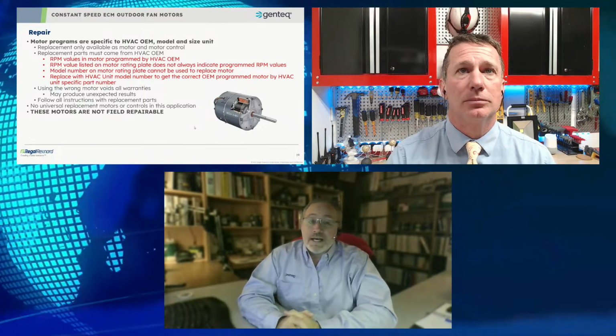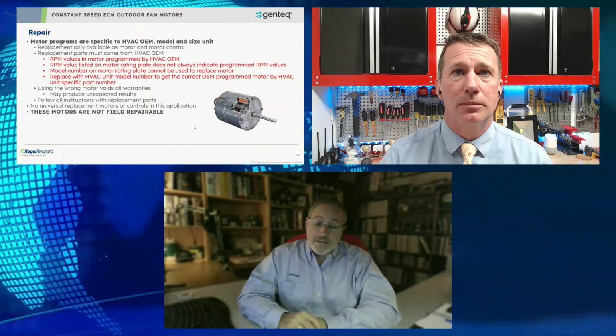Yeah, and the biggest challenges I see there are that, one, if it's not available that day, then, just like when it's 10 below in Wisconsin, we have to get the system running as soon as possible. When it's 100 degrees in Dallas or Miami or wherever, or Phoenix, you can't. That customer is not going to wait weeks or even days if they don't have to. So the technicians want to get something in there to run it. And on the price point, not to contradict what you said, but I have been hearing that the price point, at least on the outdoor fan motors, has not been coming down as much as it has on the indoor motors. You're very right about the indoor motors, and I think that's been because of the universal motor competition. Yep. But in the outdoor fan motors, to my knowledge, there's no universal replacement competition yet today. So the two complaints that I hear most are availability and price.